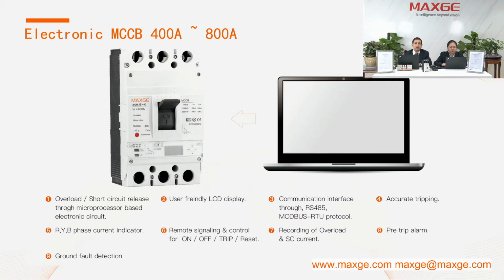The third one is the communication interface through RS485, which is the industrial standard, and Modbus RTU. We also have current and power that can be accurately measured, because we have current transformers placed inside, which are very accurate. So the current and the power can be displayed on the LCD. We do not need to put extra meters connected to the MCCB.